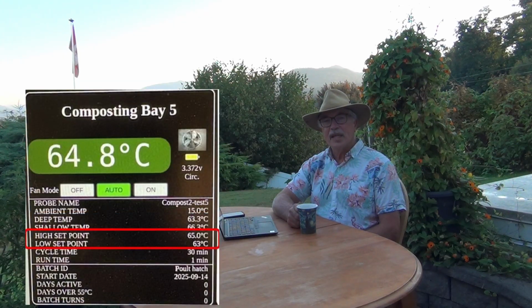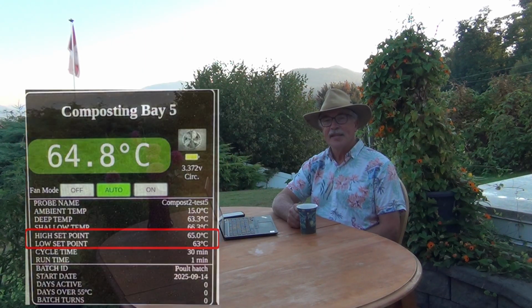I can also set the temperature at which the blowers will turn on to cool the compost. In this case, the blower turns on when the temperature reaches 65 degrees Celsius and turns off when the temperature drops to 63. The wireless probe sends the temperature information to the controller every 5 minutes, except when the blower is on because of high temperature. The probe then sends the temperature to the controller every few seconds to make sure the blower doesn't run too long, and I end up cooling the pile too much.